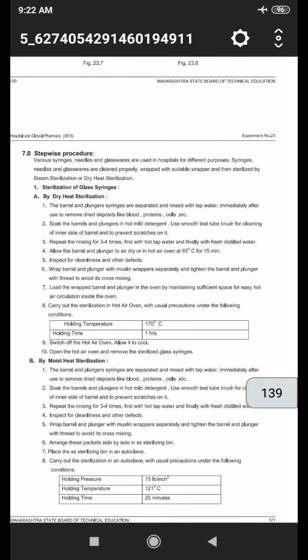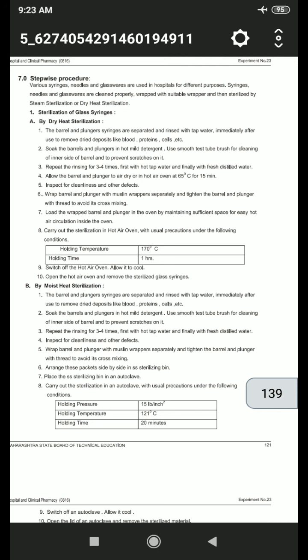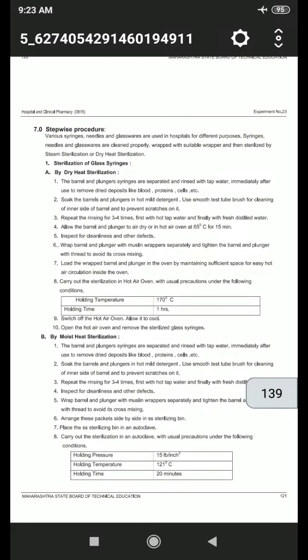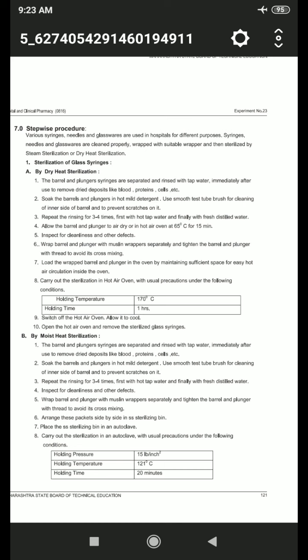Okay, now the stepwise procedure. First, various syringes, needles and glasswares are used in the hospital for different purposes. Syringes, needles and glasswares are cleaned properly, wrapped with a suitable wrapper and then sterilized by steam sterilization or dry heat sterilization. First is sterilization of glass syringe. In that, first is by dry heat sterilization and second is by moist heat sterilization. Now see the first, by dry heat sterilization. In that, first the barrel and plunger syringes are separated and rinsed with tap water. Then immediately after use, remove the dried deposits like blood, protein and cells, etc.